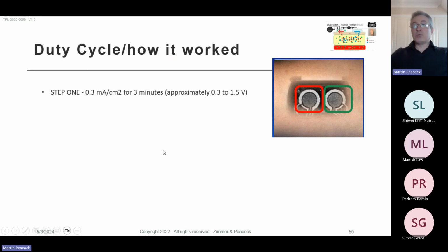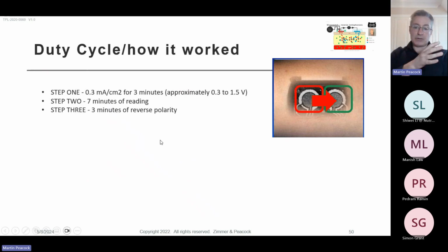But the way the watch was actually working is it was passing quite a lot of current for approximately 3 minutes, applying 1.5 volts to the skin, which is fairly high, and 0.3 milliamps per centimeter squared. And when I look at the size of the electrode, they're probably passing about 0.3 milliamps. 0.3 milliamps is quite a lot of current. So I think that was part of their problem. What they were doing is extracting the sample through reverse iontophoresis, and then measuring for 7 minutes. So they're basically integrating the signal over time. And then they would reverse the polarity and do it again.